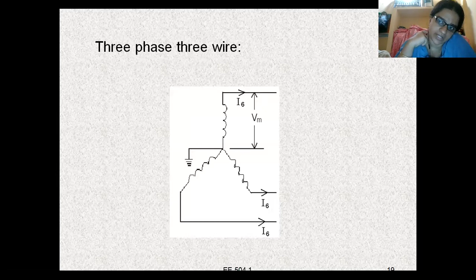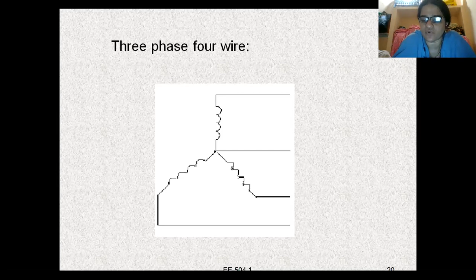Next, coming to three phase four wire system. What does this mean? Again you have three phases, meaning three windings. The end point of all three windings will be connected to a common point, and the other three end points will be connected to three wires. The fourth wire is taken from the center point where all three ends are connected. So it is called three phase four wire type of connection.